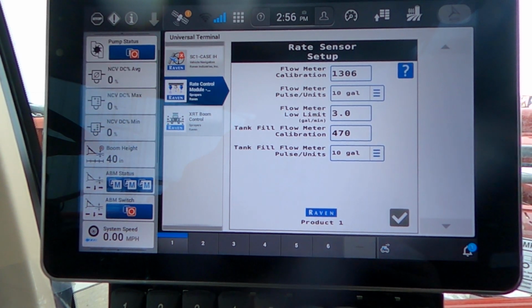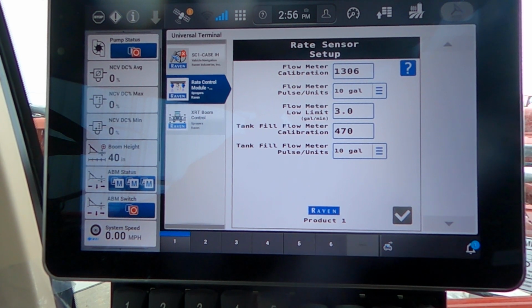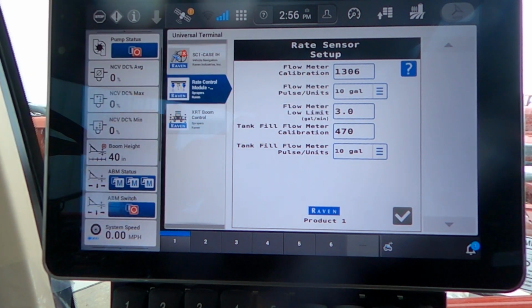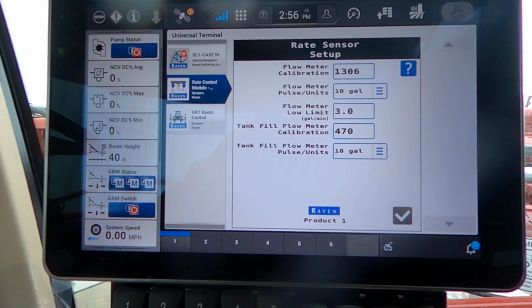Rate sensor setup. Here's your flow meter calibration. This is the number on the tag on your flow meter at the back. Those tags go missing. Good idea on your machine to take note of this in case that tag goes missing and we have to do some setup, or something happens to the monitor, we have to reset it up. If we don't have that number, we have to guess at a number and do a bunch of calibrating and figure the unit out. As well, on these machines, we have a fill flow meter underneath the tank. That flow meter number should also be recorded in your book, or take a picture of the screen and keep it for this machine. That might save you a lot of grief down the road.